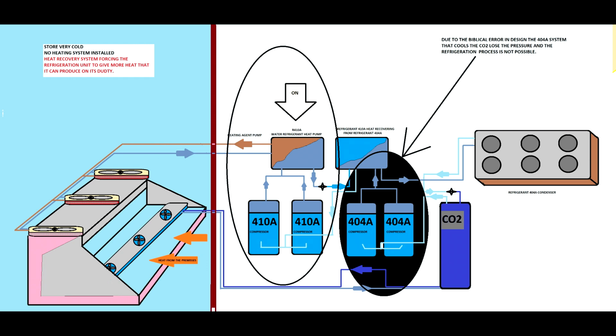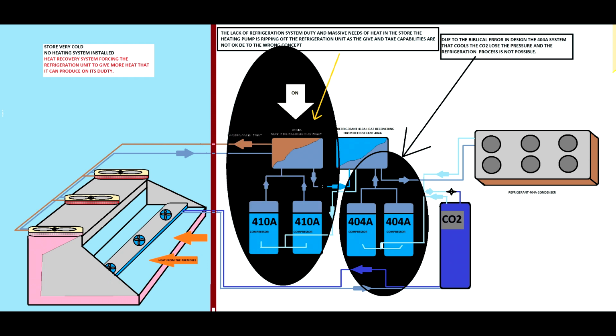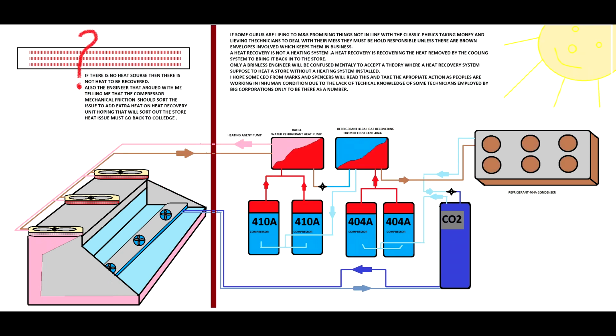The problem is the 404A works on a duty demanded by the product. If the product is cold enough, there won't be any duty on the 404A. But because the store is very cold, the 410A is forcing it, dropping the refrigeration capability so badly that the 404A no longer has the capability to cool the CO2. Then the pressure in the CO2 rises to the sky and it blows up.